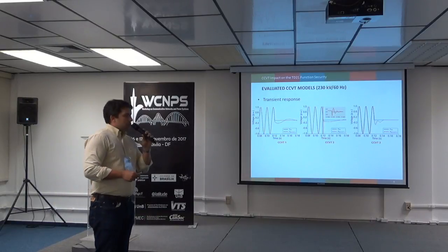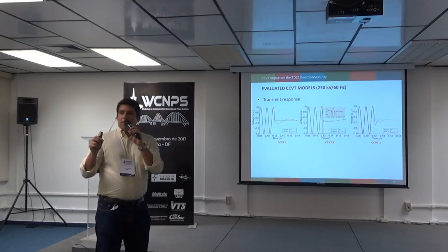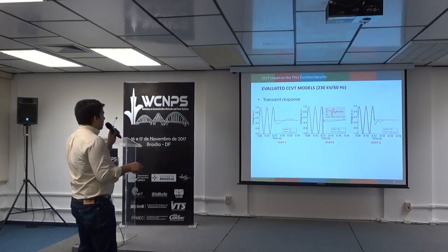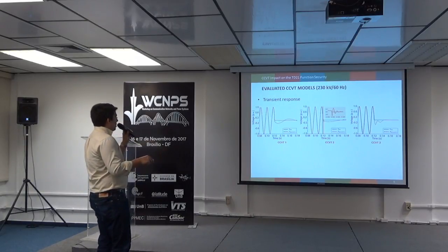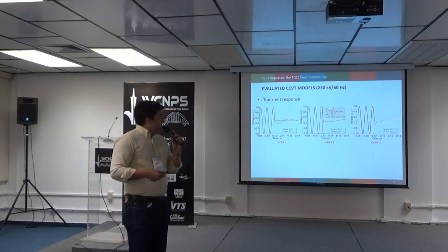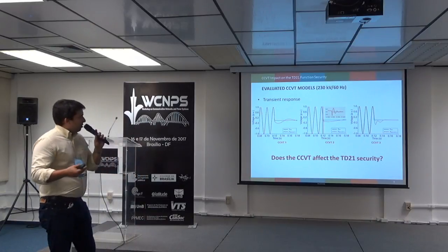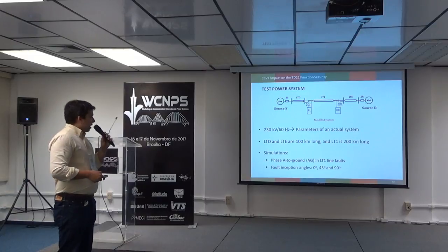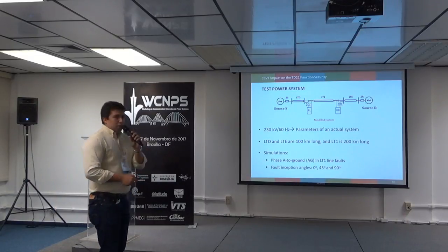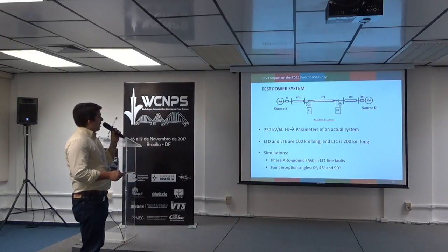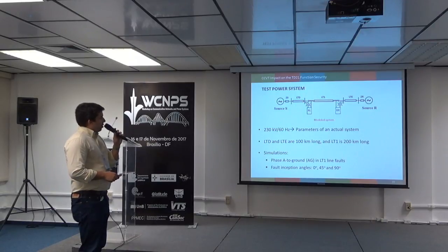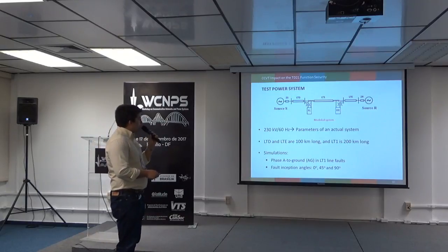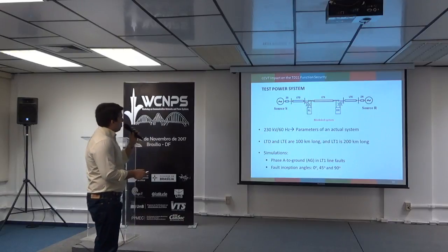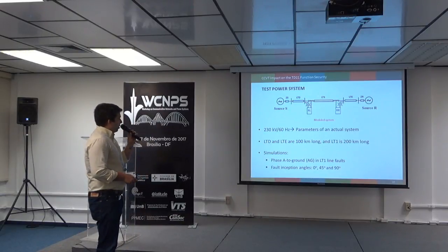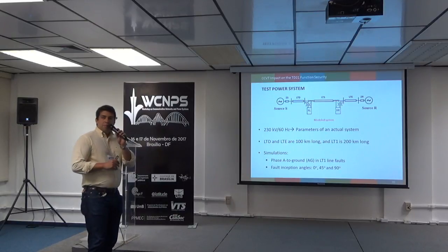To illustrate the transient response, we simulated a fault with the inception angle at 0 degrees, just to show you that while the primary voltage stays at 0, the secondary voltage oscillates due to the energy stored in capacitors and inductors. So we have a problem, and our question is: does the CCVT affect the TD21 security? To test this, we simulated a very simple system using the Alternative Transients Program. We took a transmission line with adjacent lines, which were modeled using actual parameters. The adjacent lines are 100 kilometers long, and the protected line is the LT1, which is 200 kilometers long, and some AG faults were simulated considering different inception angles.